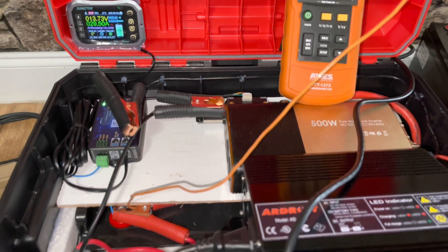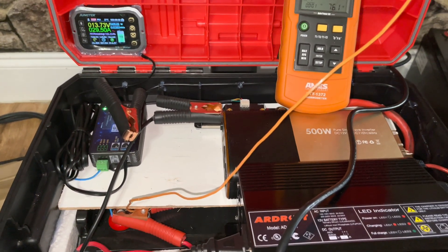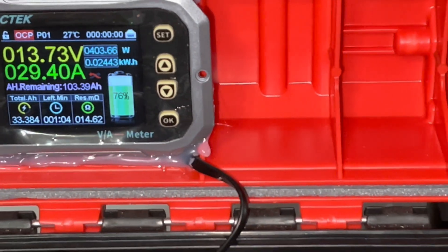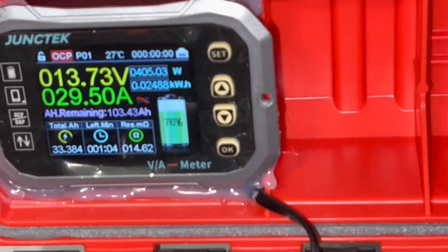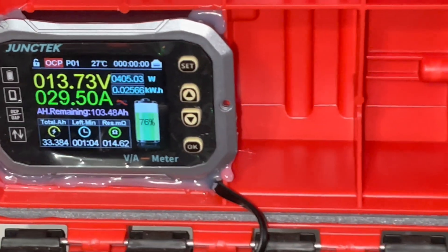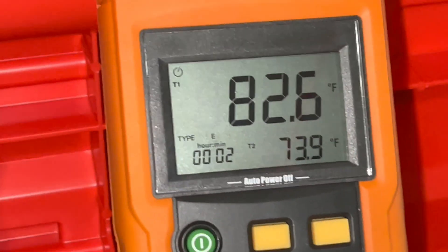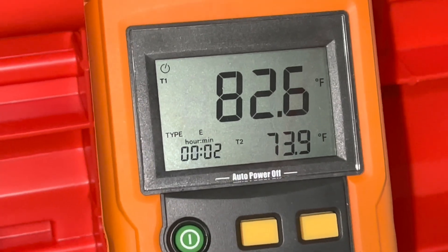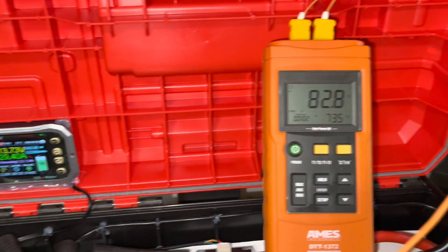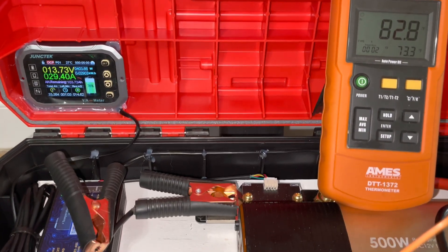We're also monitoring the temperature on the terminals, the battery, and the ambient air. The battery is about 27 degrees Celsius, which is around 81 degrees Fahrenheit. The positive terminal post is reading 82.6°F and the ambient air temperature outside the box is 73.9°F. We'll monitor those closely — the battery temperature should be close to the terminal output temperature since that's where the temperature probe is situated.